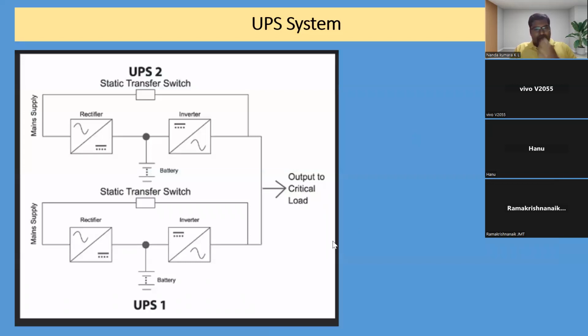Okay, then come to parallel UPS. Now all the offices have parallel UPS because parallel UPS is the future. In that we can have multiple standby options, which will avoid the downtime. If it is a single standby or standalone UPS, there will be a chance of failure. But with parallel UPS, there is no chance of breakdown, because in case one UPS trips, the other will take the load. So you can see how the configuration is connected.